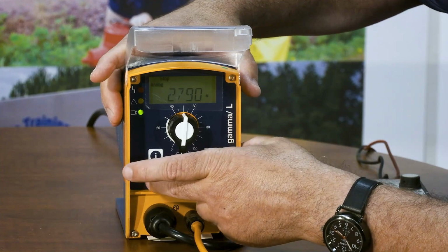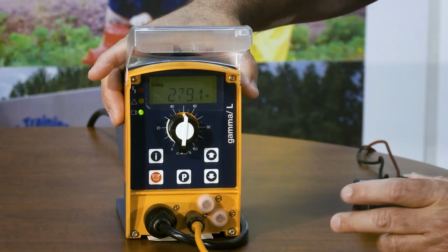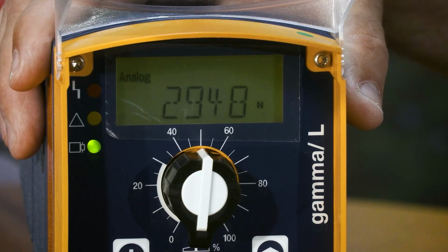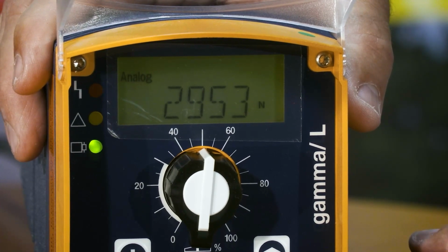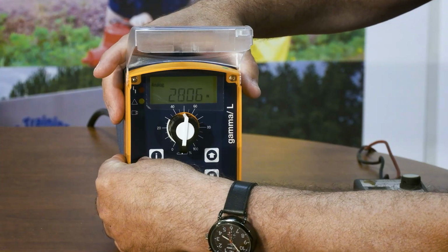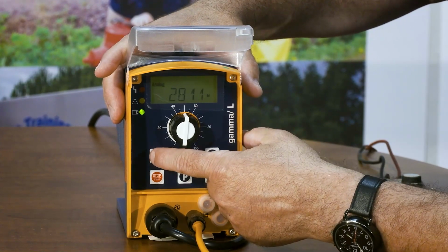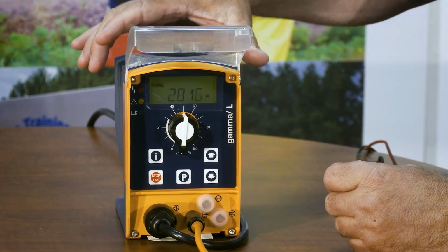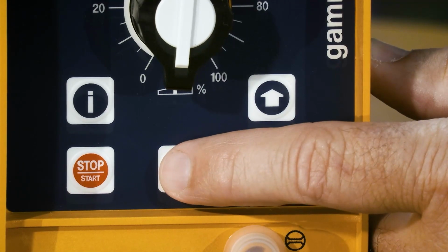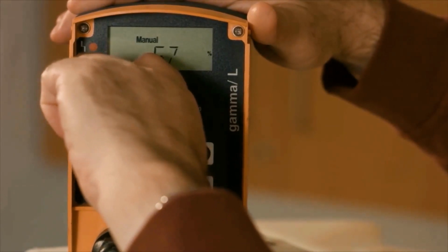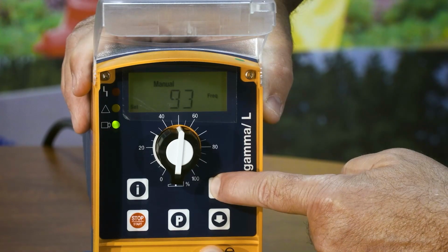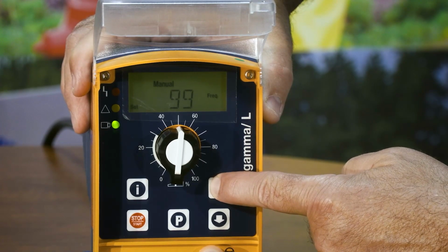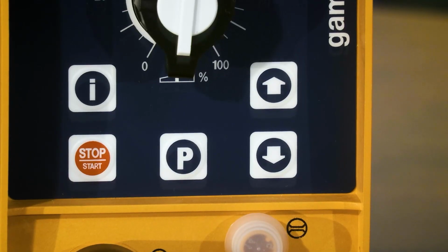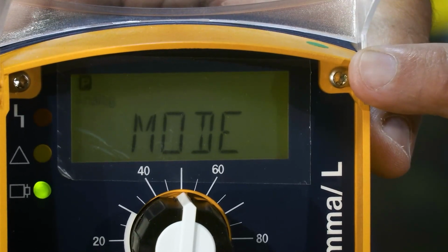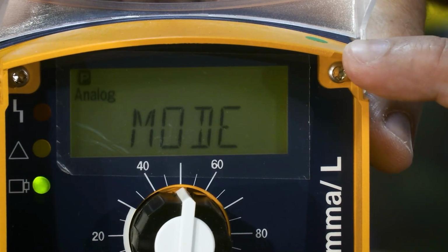This signal increases or decreases with the system flow rate. The setting of the flow range is also important. It is normally set between the maximum design flow for the system and zero flow. If the flow range was expanded, then the chemical dosage control would be less precise. For example, if we change the high range from 50 gallons per minute to 100 gallons per minute, at 50 gallons per minute we now get half the frequency. The narrower the range window, the more precise the chemical dosage control is.